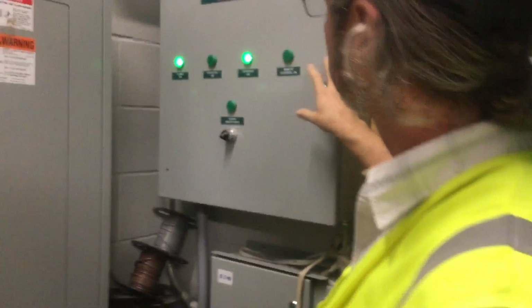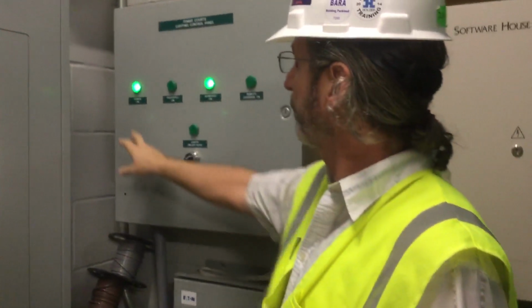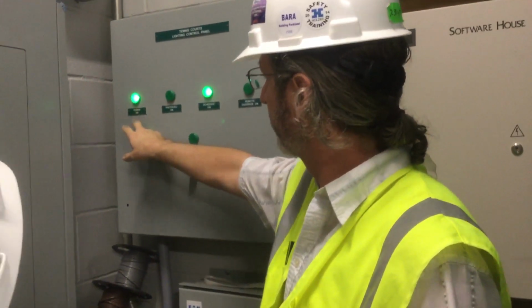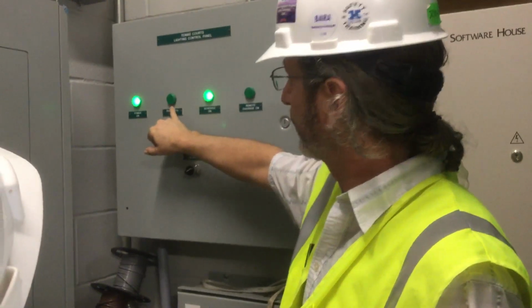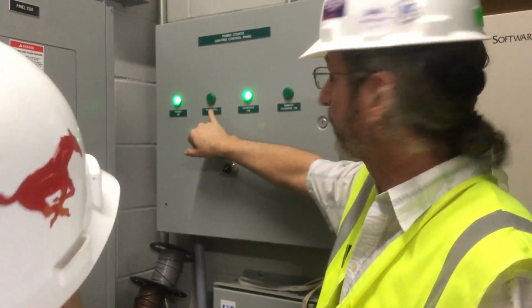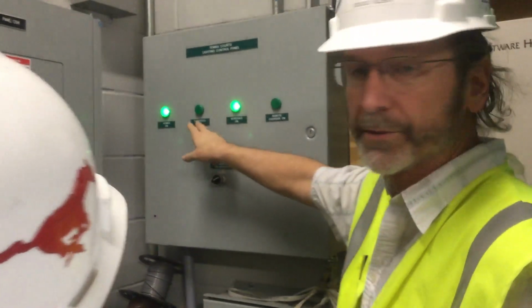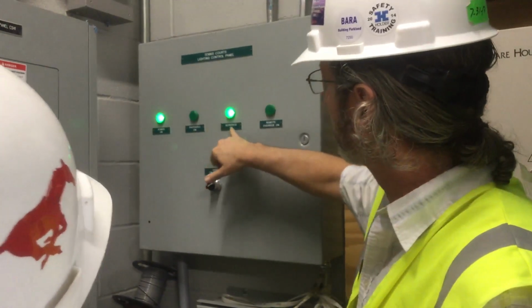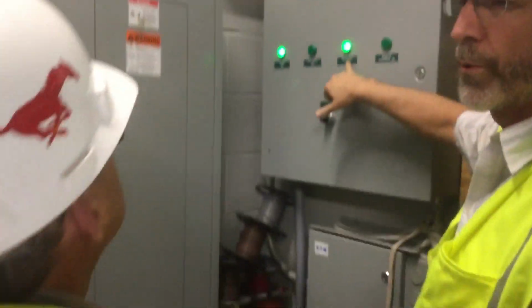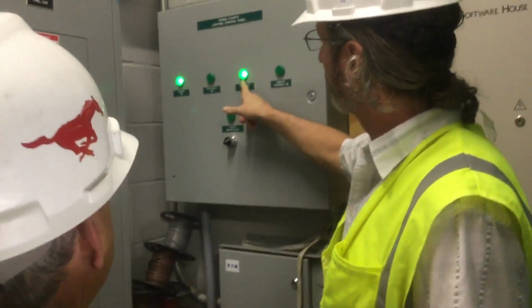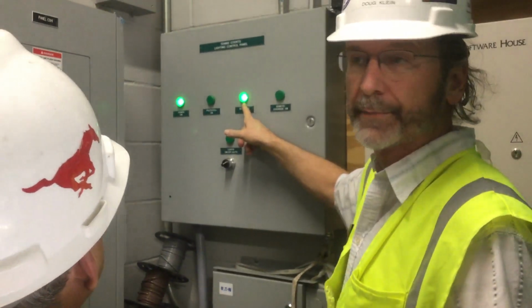On the front of it, we've got some indicators - just control system power available or not coming in. The photocell light will turn on when the photocell thinks it's dark, so that's a good gauge as to what's happening. It's off right now since we're in the middle of the day. The schedule indicates we're within the schedule window, coming off channel 1 of the time clock. This light will turn on at 6 in the morning and turn off at 10 p.m. until you change it.